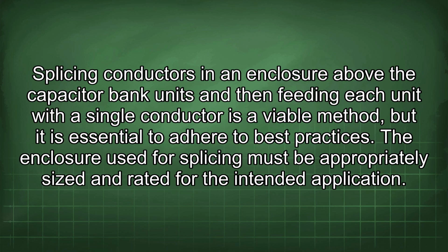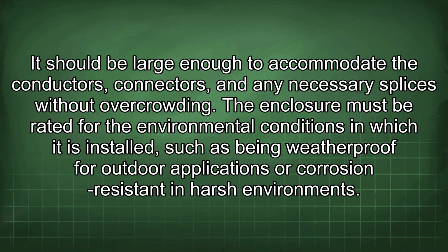Splicing conductors in an enclosure above the capacitor bank units and then feeding each unit with a single conductor is a viable method, but it is essential to adhere to best practices. The enclosure used for splicing must be appropriately sized and rated for the intended application. It should be large enough to accommodate the conductors, connectors, and any necessary splices without overcrowding. The enclosure must be rated for the environmental conditions in which it is installed, such as being weatherproof for outdoor applications or corrosion resistant in harsh environments.